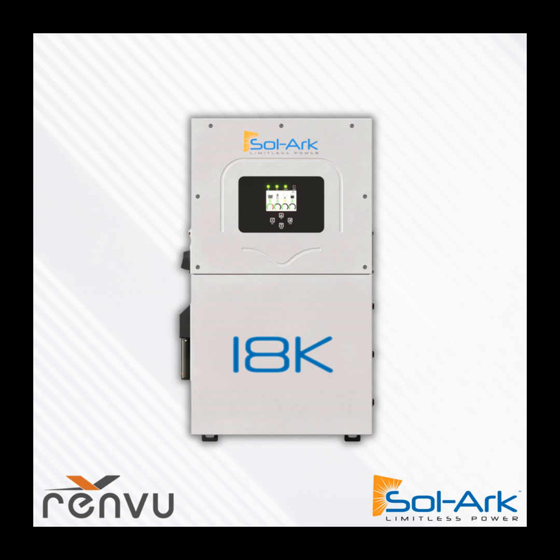The 100 milliamp power for the 15K was not conservatively spec'd, and by the time you get into MLPE with monitoring or optimization, the amperage would often fluctuate above 100 milliamps. So as the asker of that question knows, with a 15K you really have to use the external AC power supply for your rapid shutdown system.